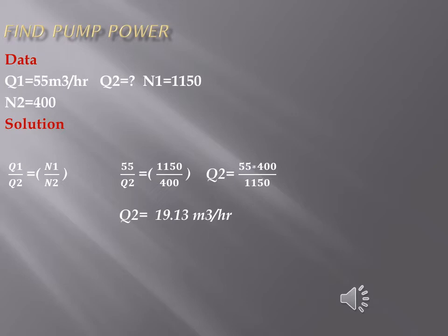q1 is given, n1 is given, n2 is given. The formula is q1/q2 = n1/n2. We have n1, n2, and q1, but we have to find q2. Put all the values into this formula and we will get the answer: 19.13 meter cube per hour.